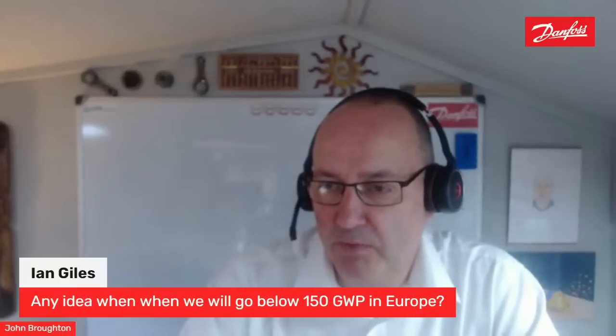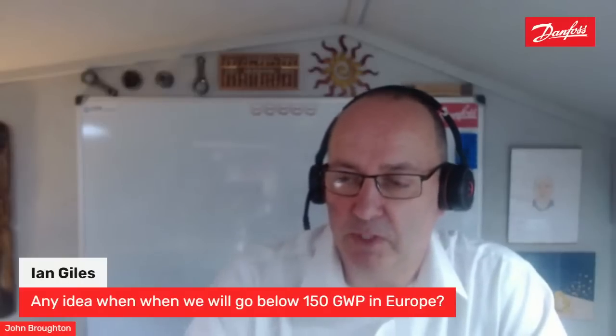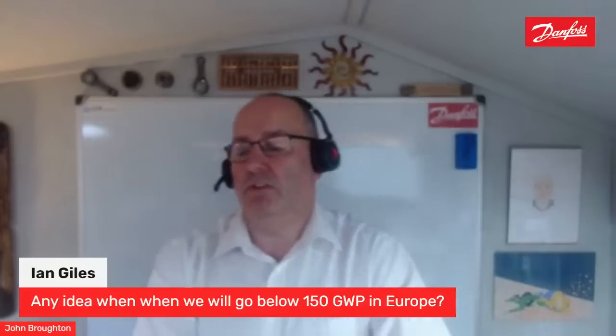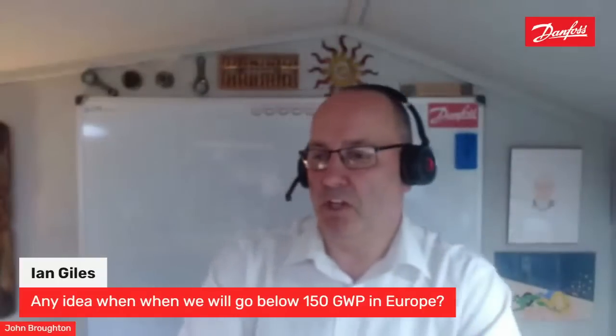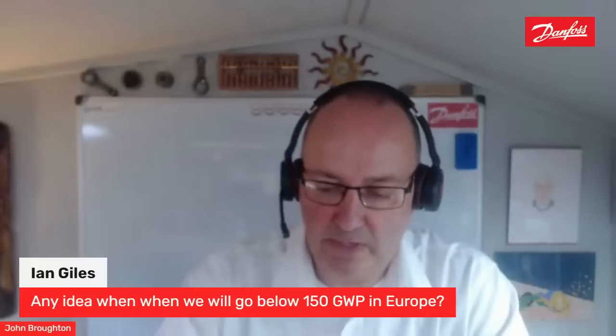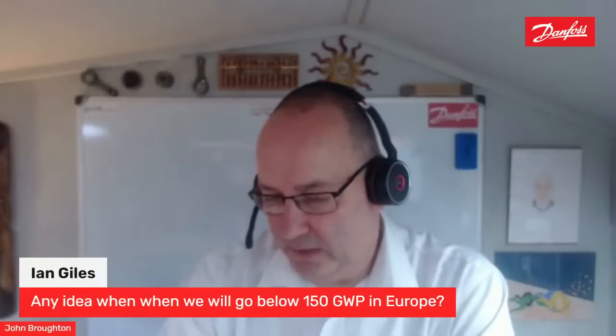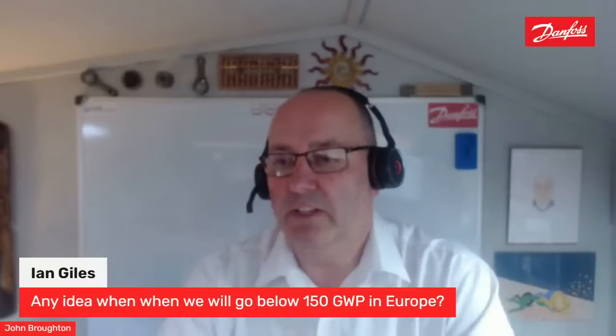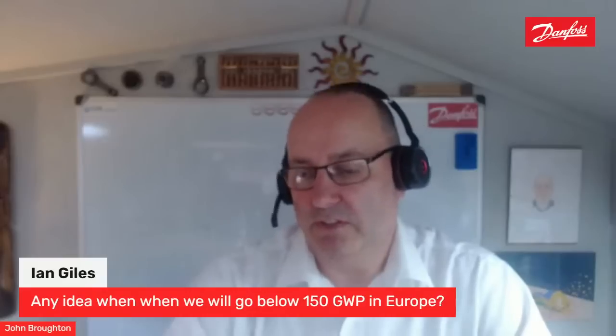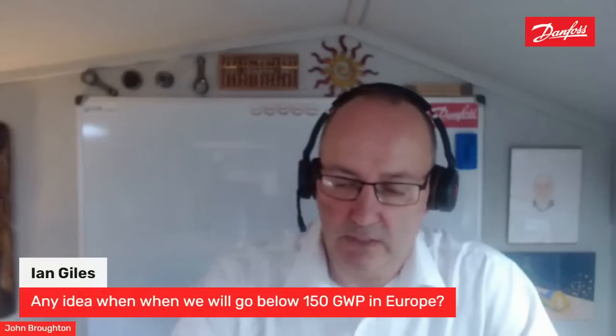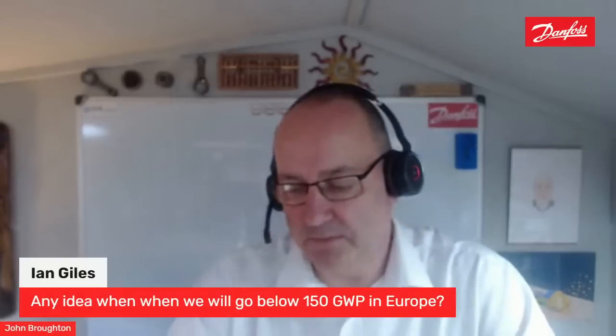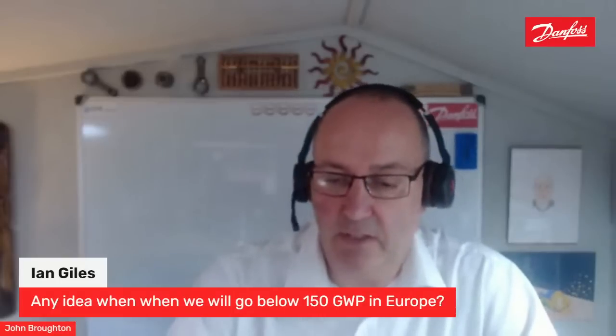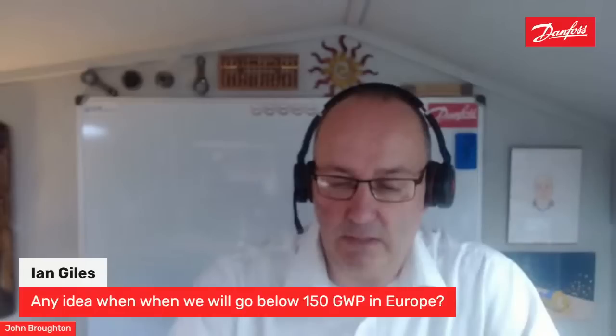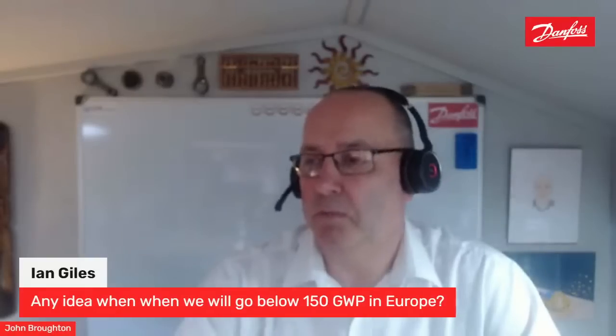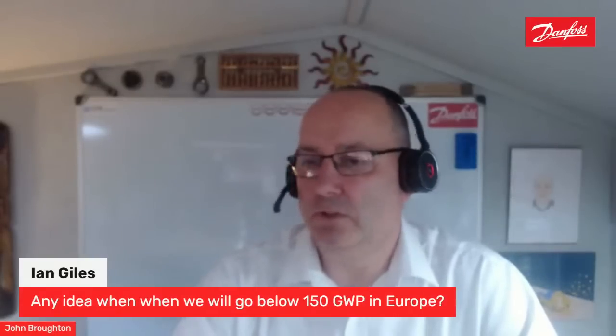Any idea when we'll go below 150 GWP in Europe? Basically, that's about 2030. So we've got about 10 years to go when we'll be asked to go to that sort of level of GWP, which, as I said, will either be the CO2, ammonia, and the hydrocarbons and the A2L, so the A3 refrigerants and the A2L, so the flammable and the mildly flammable refrigerants.